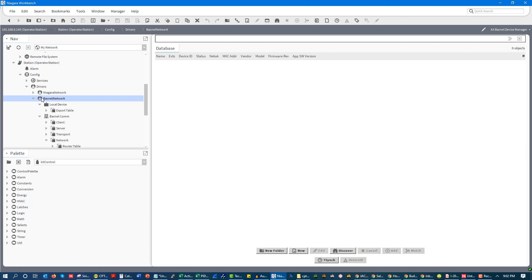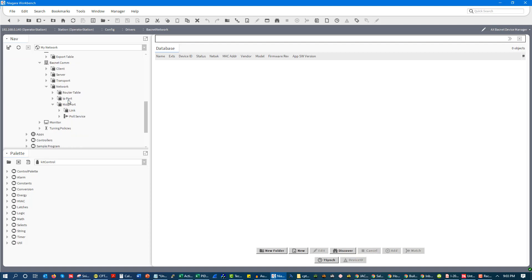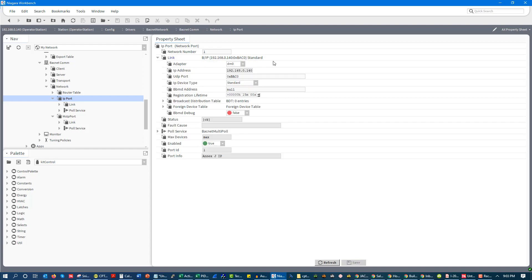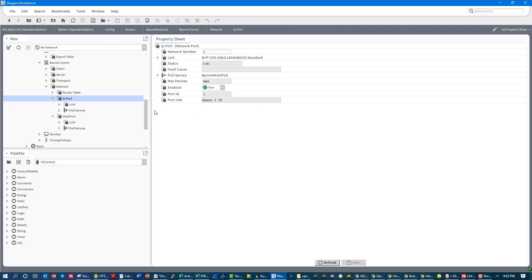So what you'll see with a BACnet network is that you have kind of two types. You have an MSTP port, also known as an RS-485 port, and an IP port. IP is all the rage lately. This is what everyone seems to be largely interested in. And so what we can see right here is that we have our network number, our link for our BACnet IP. You can see it has a standard UDP port. You have your port, you have your IP address, you have all of these settings. And all of this comes together in order to enable you to communicate with controllers.